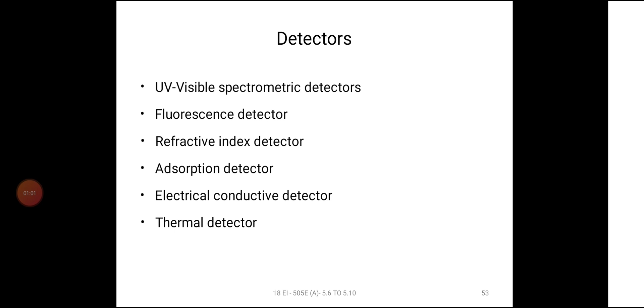The individual components exiting the column are detected by the UV visible spectrophotometer, fluorescence detector, refractive index detector, absorption detector, electrical conductivity detector, or thermal conductivity detector. Any of these detectors can be coupled to the end of the column. We convert the non-electrical signal into an electrical signal. The electrical signal is connected to the potentiometer recorder, which records the amplitude versus time function. Each peak value gives the concentration of individual components present in the sample mixture.